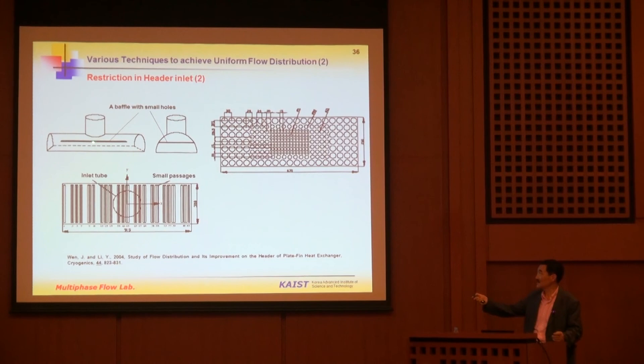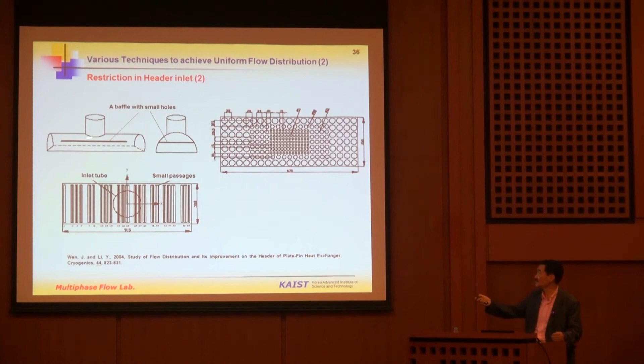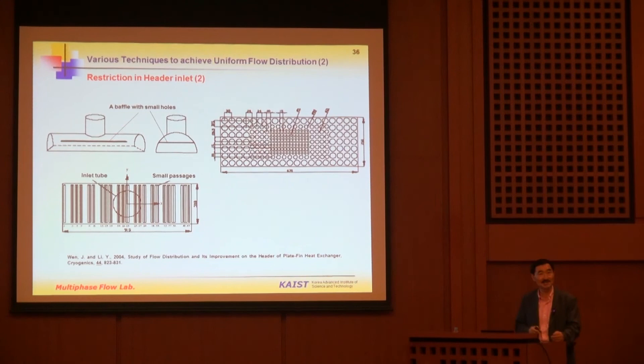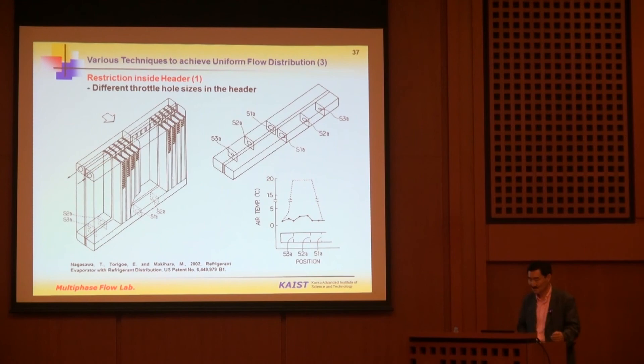Another technique is placing a baffle inside the header. Near the header inlet, the holes in the baffle are very small, giving higher friction and flow restriction. Further from the inlet, the holes are larger. The key information — how to choose the hole size and the spacing between holes — is patented in many heat exchangers.